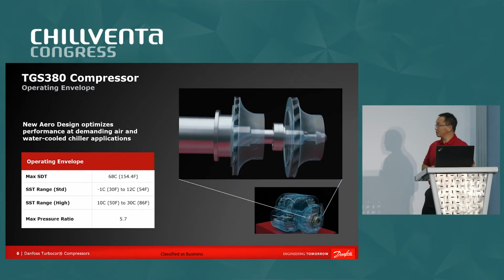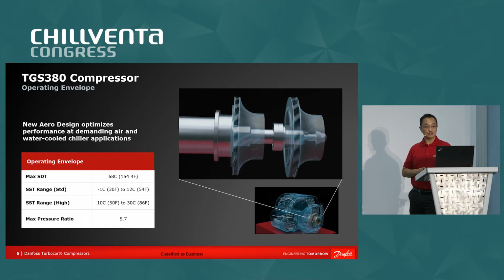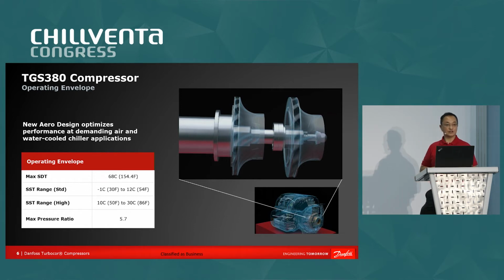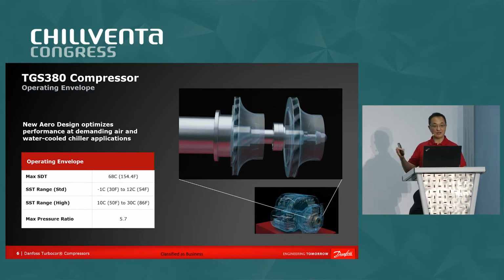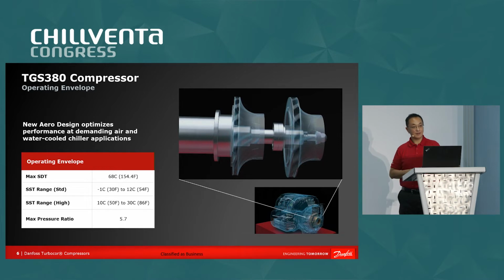So let's talk a little bit more specifically about the operating map capabilities of this new compressor. What we did with this compressor is that we changed the impeller profile, or the aero, such that it can be optimized for use in these high lift, high pressure ratio applications. So what are the key boundaries to take note of? This compressor can achieve a maximum saturated discharge temperature of up to 68 C. So it's a very good solution for heat pump applications, such as heating potable water or domestic hot water applications, or for space heating.